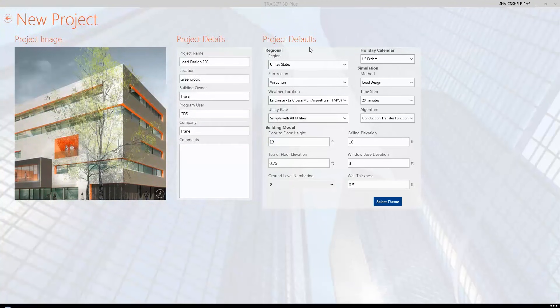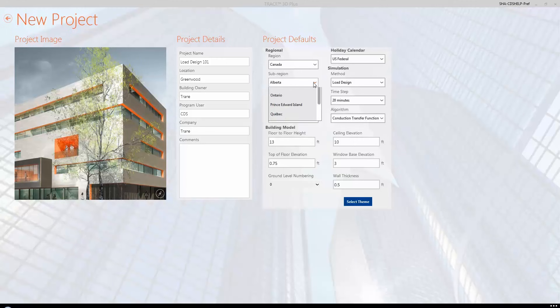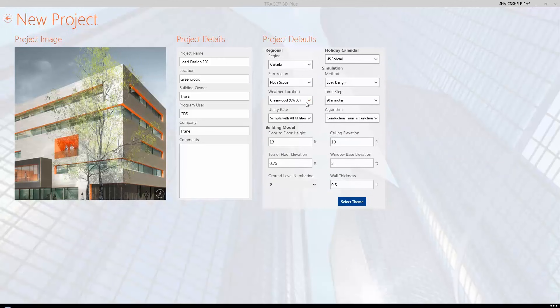The project default section allows us to set the weather location, the simulation mode, and the building model default dimensions. Many of these building model defaults will not be editable elsewhere within the project, so we need to make sure they are correct before proceeding. Additionally, anything changed in the project default section in the current project will remain as the new default when a new project is created. Let's get started with our example by entering the project defaults. To select the weather location, click the region drop-down, then select Canada. Next, change the sub-region to the province of Nova Scotia. Finally, choose Greenwood as the weather location. If needed, you will be able to change the weather location and design conditions in the building section of the program.